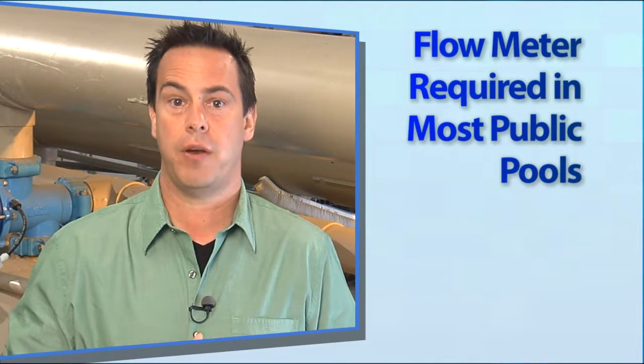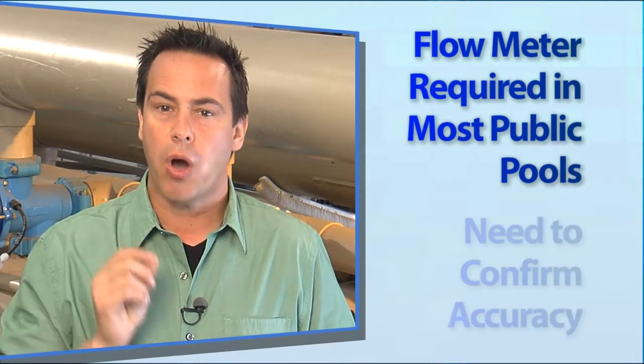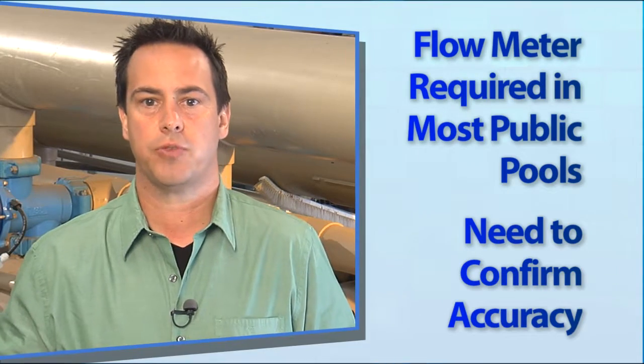In this module, we'll look specifically at how to measure flow rate and determine the system's total dynamic head, or TDH. All covers listed to the ASME A112.19.8-2007 or later standard have a published flow rate. This published flow rate is often different for floor and wall mounting. Most health and building codes require a flow meter in public pools, but we also need to confirm that the flow meter is reading accurately.